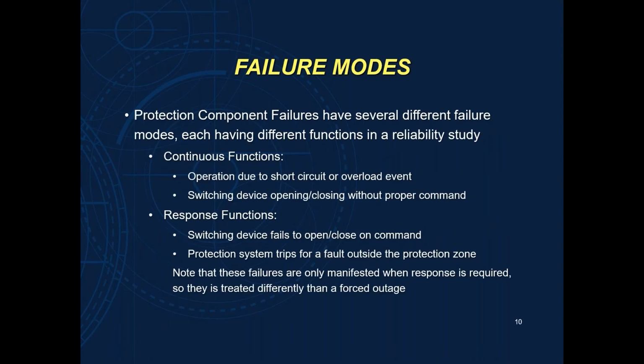For protection components, you can have a whole string of different things that can happen. You can have a circuit breaker that doesn't close when you want it to close, or you can have a short circuit trip that causes a trip of your system, right? There's a lot of different ways that a protection component can fail. And there's also a lot of engineering design that goes into preventing these things from taking unnecessary outages. Some of these are going to be a little bit different, because when we're talking about protection components and failures that happen as a response to an event, the only time that's going to happen is when it's called upon to act. That's not exactly the same type of failure rate as a component failure rate based off of a mechanical failure or just aging, okay?